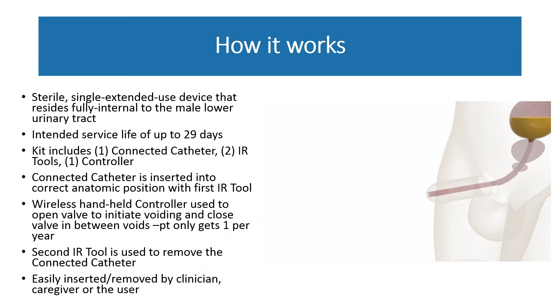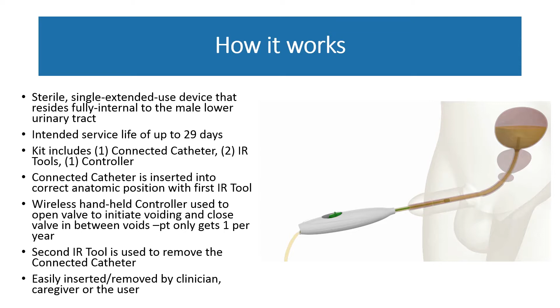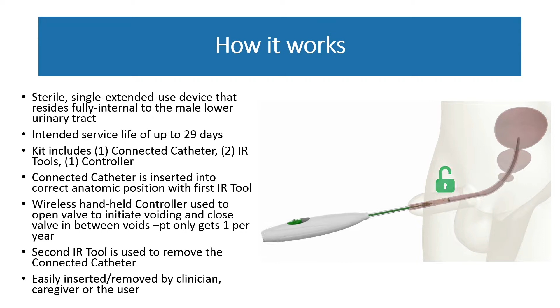An intraurethral catheter that has, sort of, a turbine on it. It has a magnet. So it's a single catheter, but within the catheter there are eyelets at the end for drainage. There's a sort of retaining, dilating area that's going to be at the bulbous urethra. It's going to be 22 French. The catheter at the tip that's in the bladder is actually 16 French. There's no retaining balloon. The device is simply placed in with this instrument that you saw. It unlocks it. There are 3 sizes of this device, so you'll have to do cystoscopy to make sure you get the right size. When you put the electromagnet on it, it will stimulate and the valve will open.